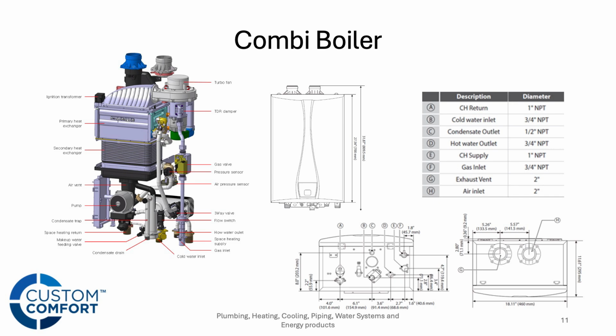So looking at some of the specs and components of the combi boilers, these are all vented in 2-inch. All the boilers we're going to talk about tonight are going to have 2-inch tappings on the top. Your central heating connections are going to be 1-inch. Again, the combi is going to have 3/4 domestic inlet and outlet. It's got a 3/4 gas line. And that's kind of the rundown on the connections and tappings that we have on the combi boiler.